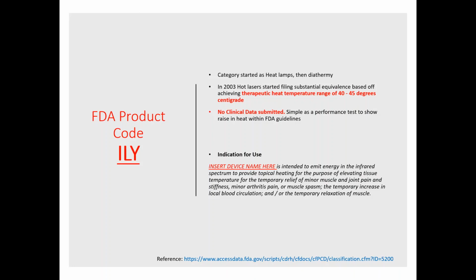So within laser therapy, there are 2 different categories within the pain indications for FDA clearance. The first is ILY. This category started way before 1976, and it was heat lamps. Then you started having diathermy, substantially equivalent to the heat lamps based on creating heat. So in 2003, class 4 lasers or hot lasers started as substantial equivalents based on a therapeutic heat range of 40 to 45 degrees Celsius. So there's no clinical data required to get the ILY code. It's as simple as submitting bench testing showing your device can create heat at 40 to 45 degrees Celsius and not beyond that point.